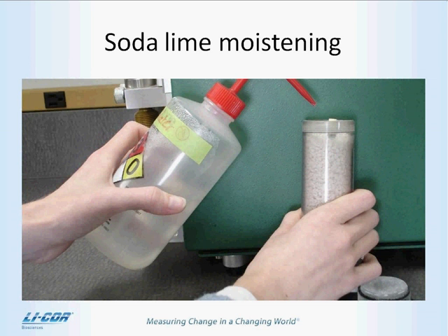Elizabeth, can I interrupt with a question? Sure, I'd love to take a question. How often can soda lime be reused, and what happens when it can't be used anymore? Oh, that's a good question. Typically, soda lime can be reused multiple times. We've got some customers who've told me that they've been reusing and regenerating their soda lime for about a year now. I think that's the maximum people have used it. But towards the end, you may notice that it's turning violet or it's getting a little bit crumbly or even regenerating isn't doing it. And at that point, it's time to switch out your soda lime.